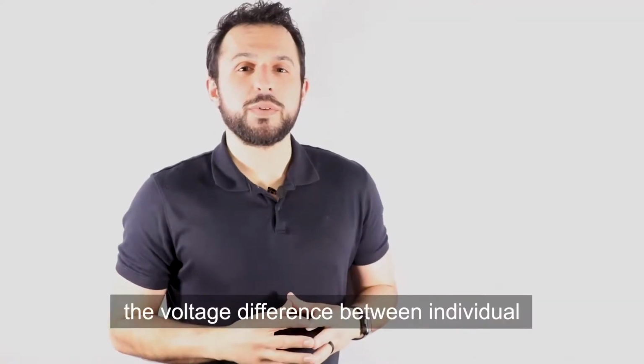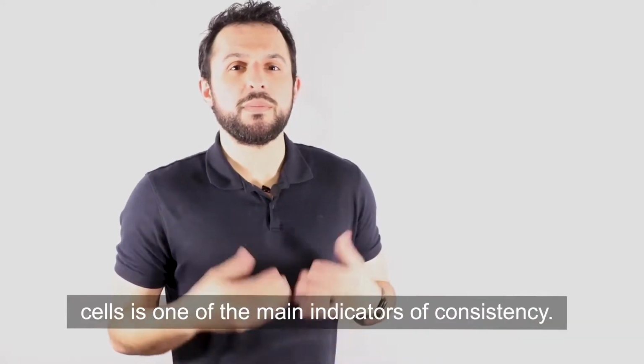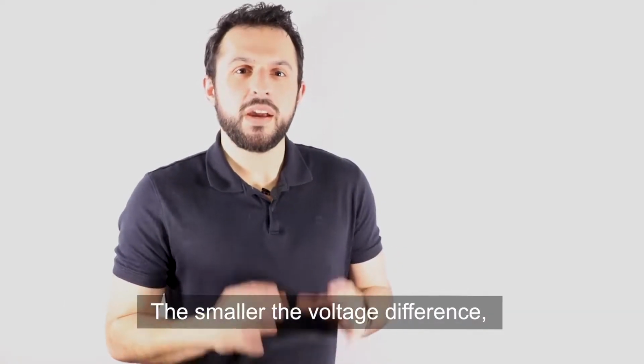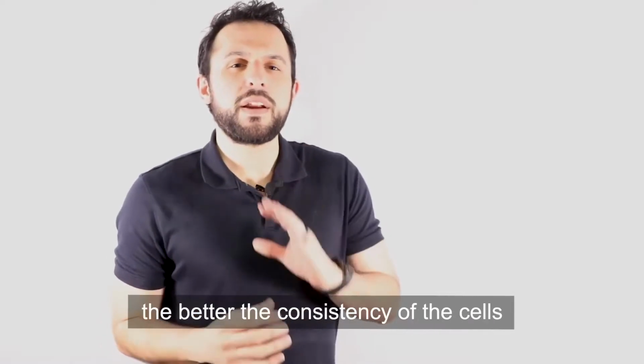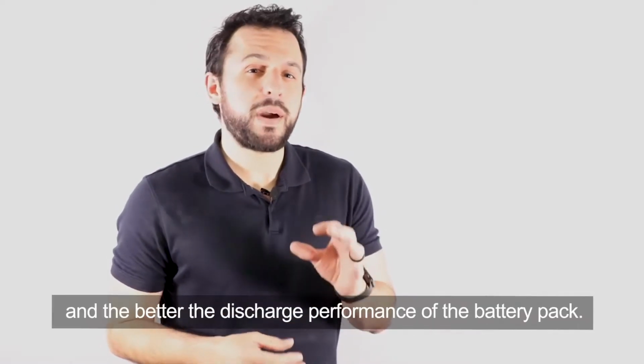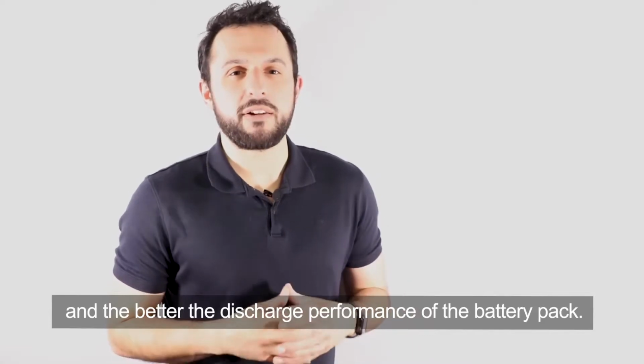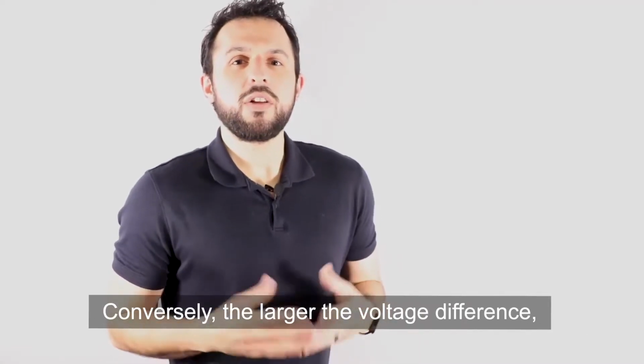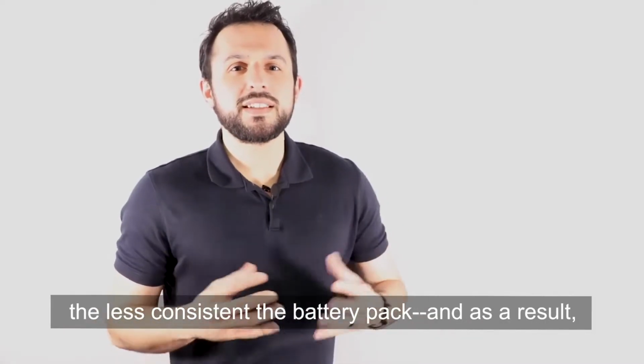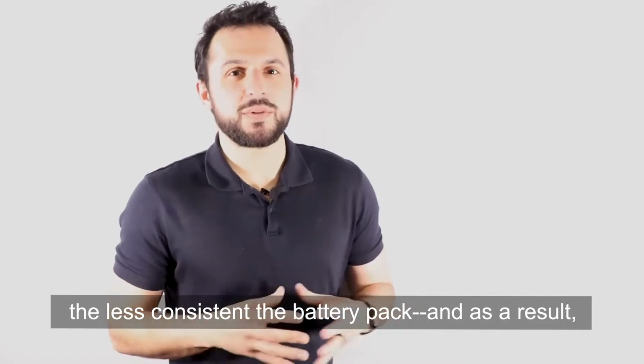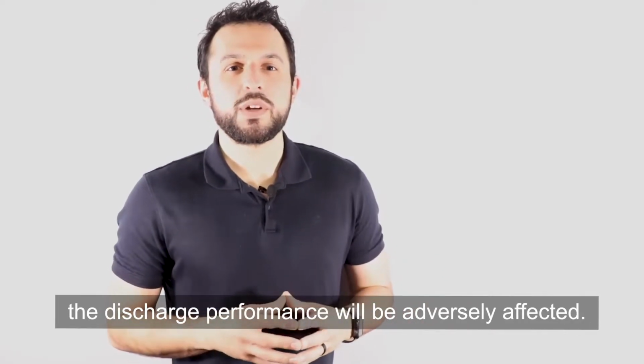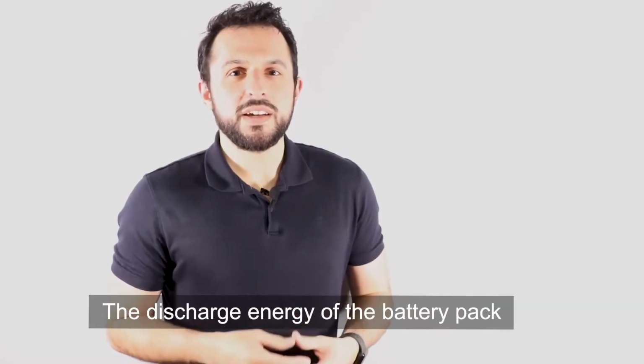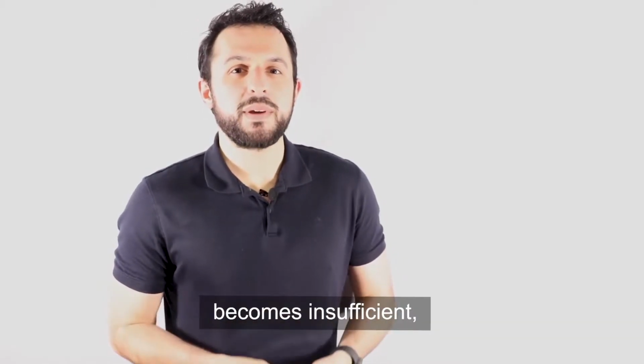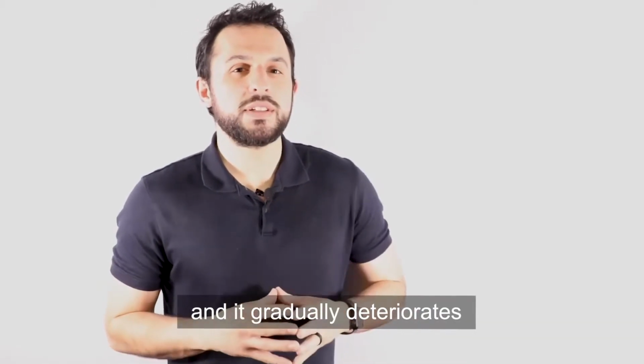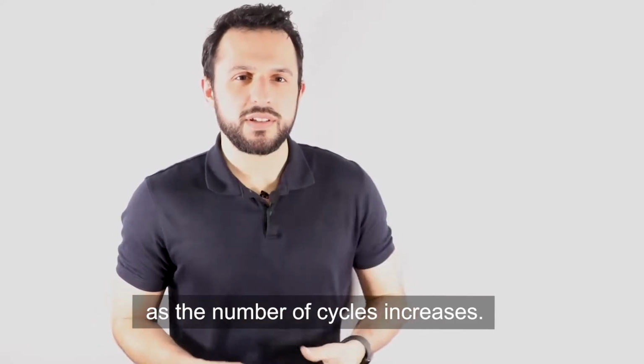For battery packs, the voltage between individual cells is one of the main indicators of consistency. The smaller the voltage difference, the better the consistency of the cells and the better the discharge performance of the battery pack. Conversely, the larger the voltage difference, the less consistent the battery pack, and as a result, the discharge performance will be adversely affected. The discharge energy of the battery pack becomes insufficient and it gradually deteriorates as the number of cycles increases.